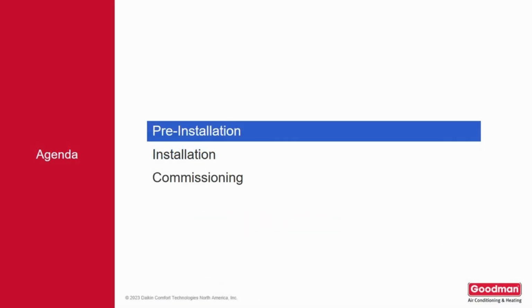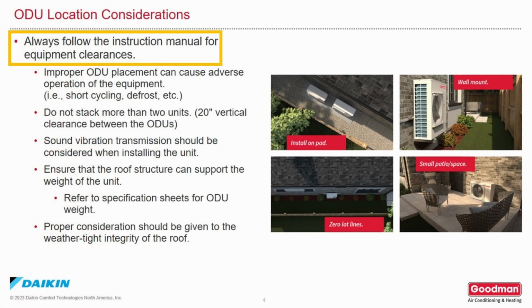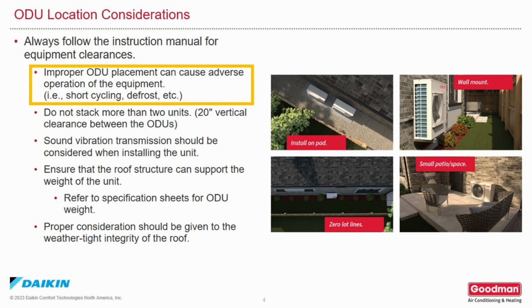Here are some pre-installation recommendations. Always refer to the installation manual for equipment clearances. Improper outdoor unit placement can affect the operation of the equipment, such as sound, unit vibration, defrost, air short cycling, and even the wind can cause a reduced capacity and efficiency of the unit.